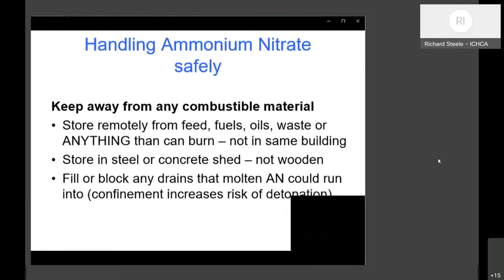Likewise, your store obviously needs to be incombustible, made of masonry or steel, certainly not wood or plastic. Another thing is to make sure any drains nearby are blocked or filled, because if AN melts in a fire and runs into a drain, that contains it, and the confinement increases the risk of detonation very greatly. And obviously, watch for smoking and hot work.